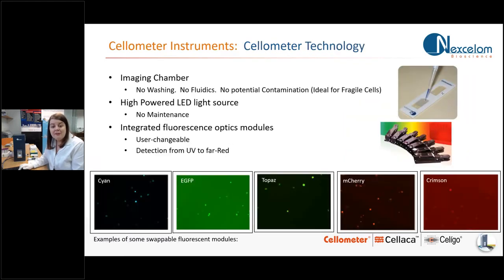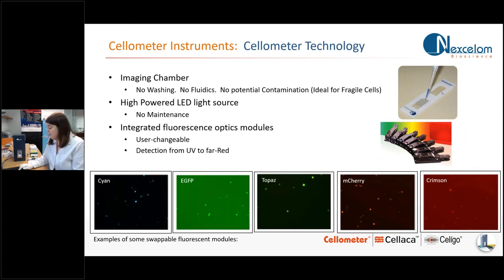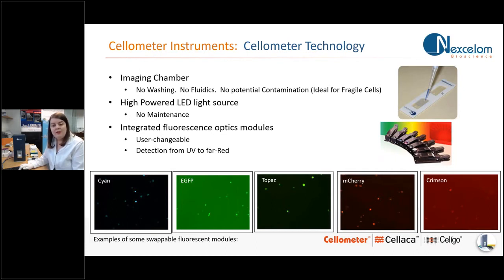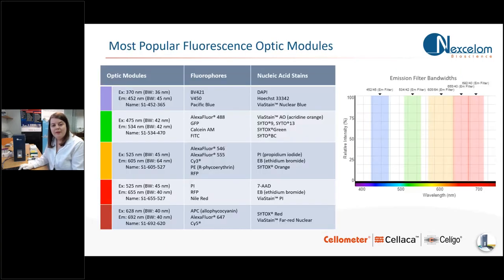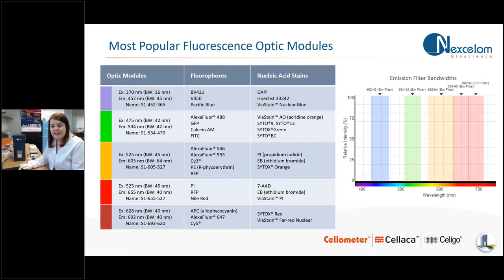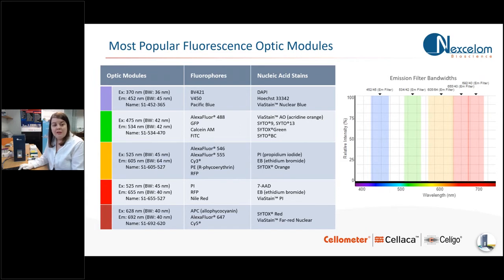And a little bit about the technology, the Spectrum images cells within disposable imaging chambers, which I'll show you. It has high powered LED light source. We use changeable optical filters, allowing for flexibility with antibodies and staining methods for your cell-based assays. And this is a list of our most popular fluorescent optic modules. And as you can see, these filters cover a large range of fluorophores and nucleic acids that can be used on the Spectrum.